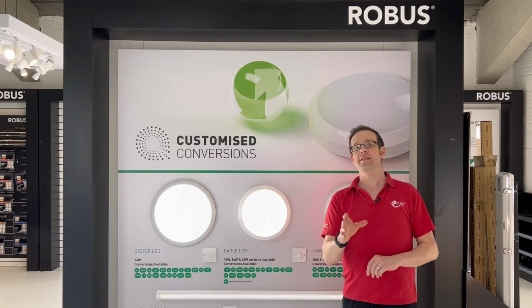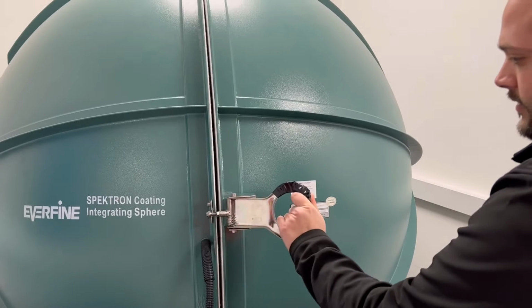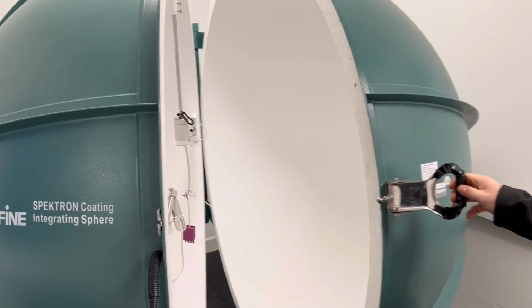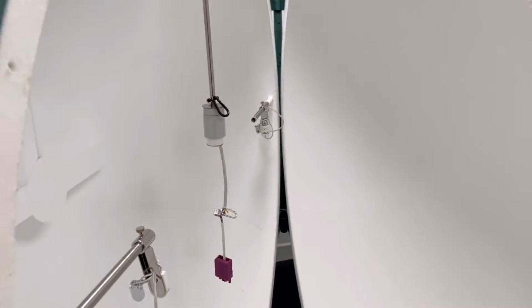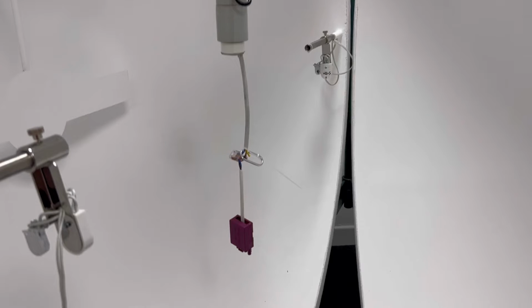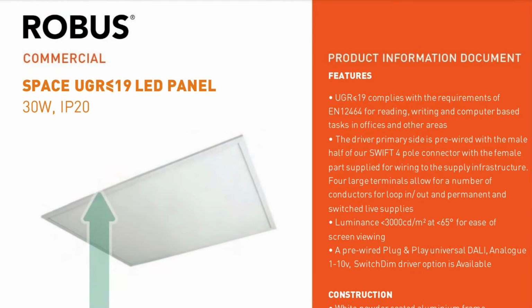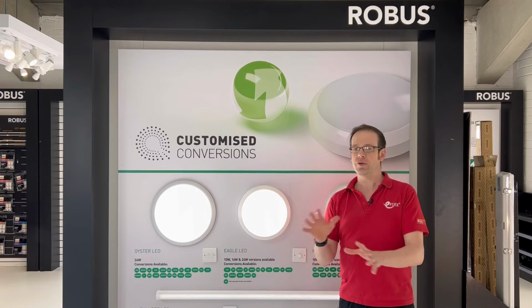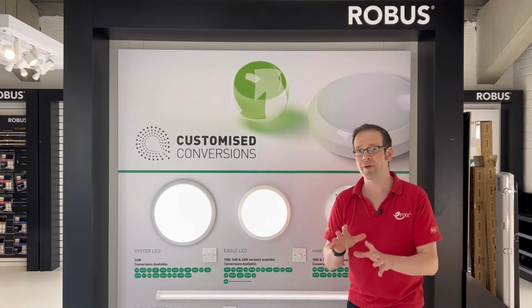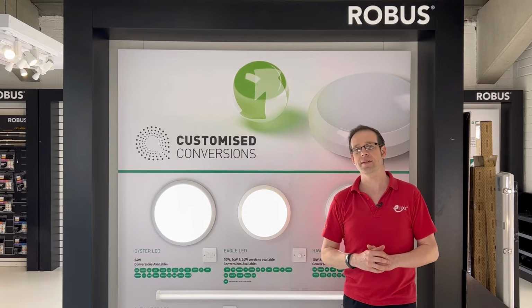To help lighting designers and installers to minimize glare, lighting manufacturers build and test their lights to minimize this effect, and you'll often see a label on a fitting that states it has a UGR, or Unified Glare Rating, of less than 19. Now, it's important to remember that there is no such thing as a light fitting that guarantees glare in a room will be less than 19.